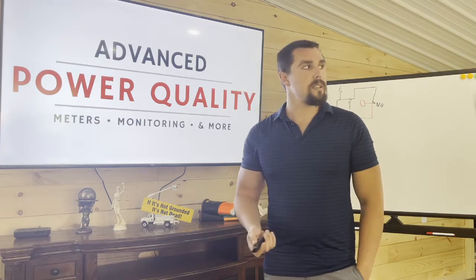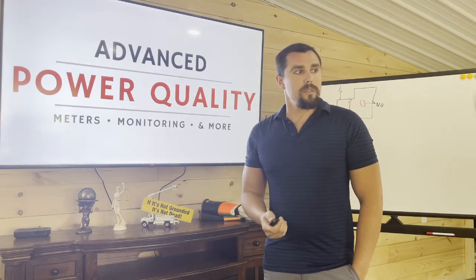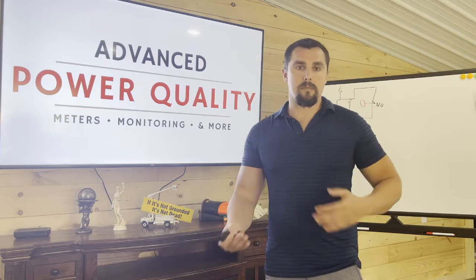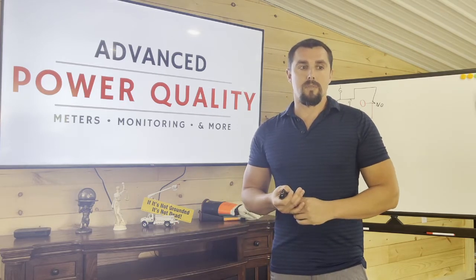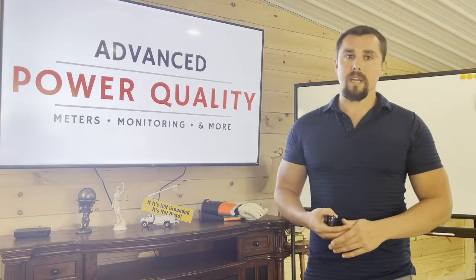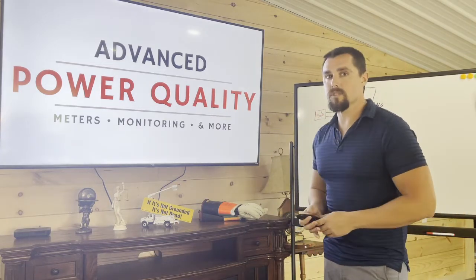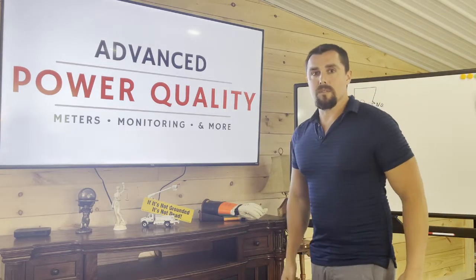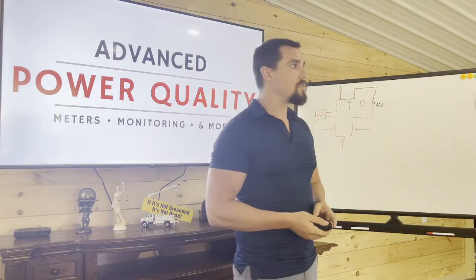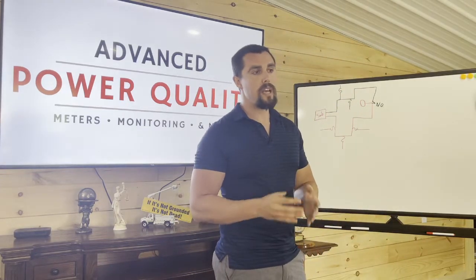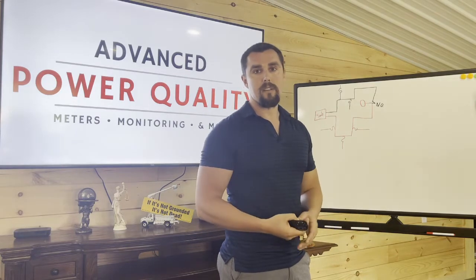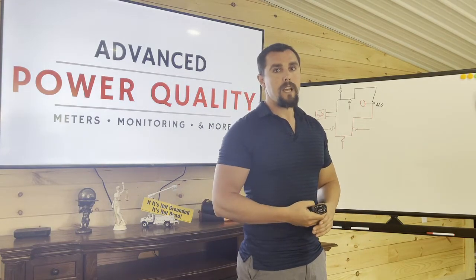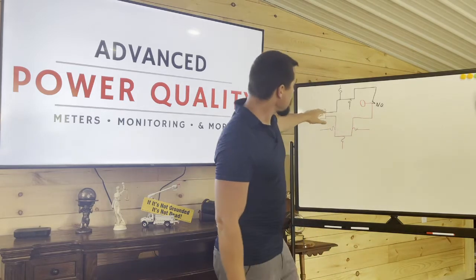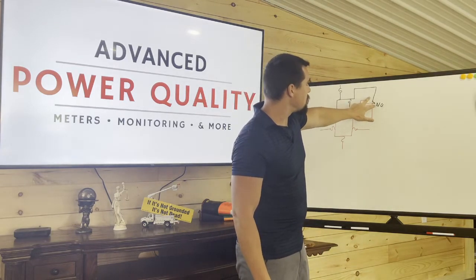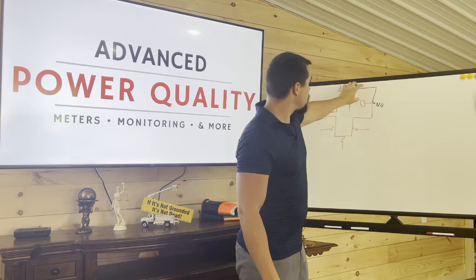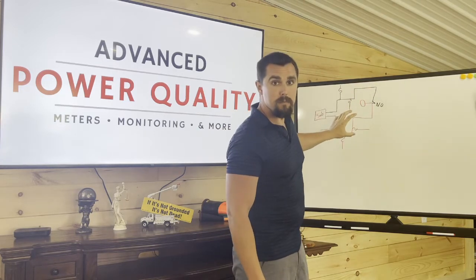One thing to discuss: when you talk to a utility about ATSs, they plan accordingly to have capacity to switch over at any time. In typical utility system planning, you shouldn't have a feeder loaded higher than about 20 to 40%. This allows your normally open points the capacity for the black feeder to pick up the red feeder.